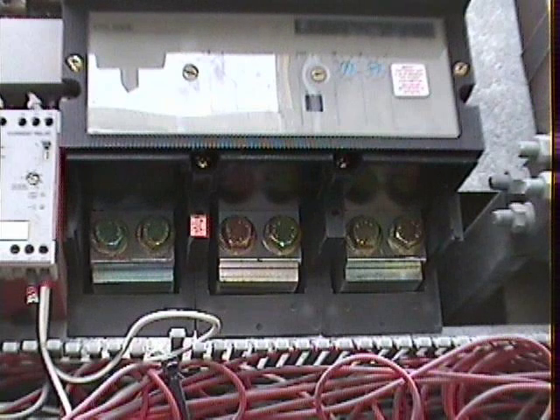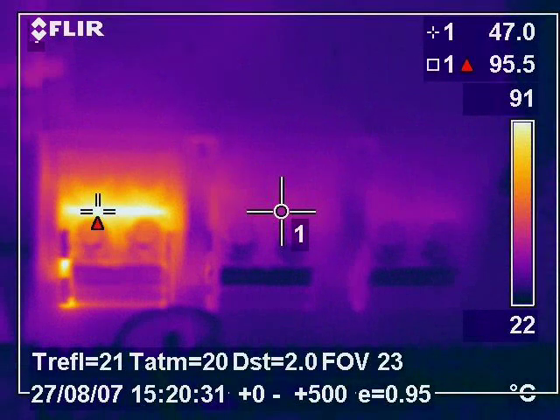This image shows the bus bar connections on a 1250 amp circuit breaker feeding a large industrial plant. The thermal image shows that an internal fault within the circuit breaker has caused a hot spot on the first phase. The thermal imaging inspection allowed this fault to be identified and the circuit breaker to be replaced without any loss of production or downtime being incurred.